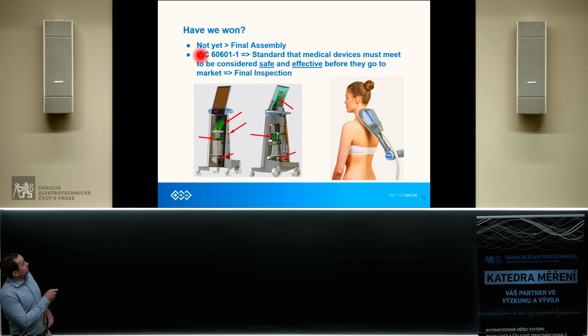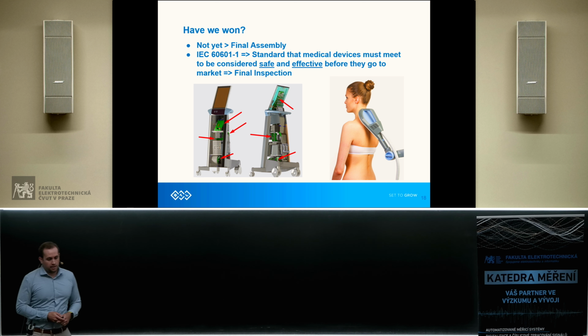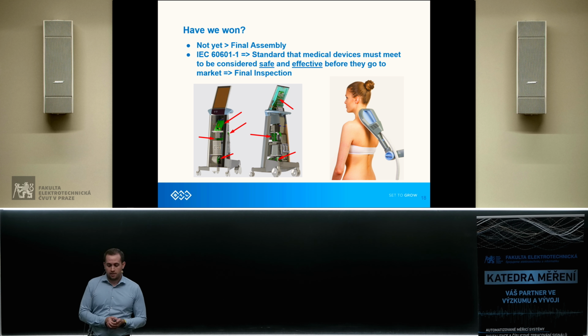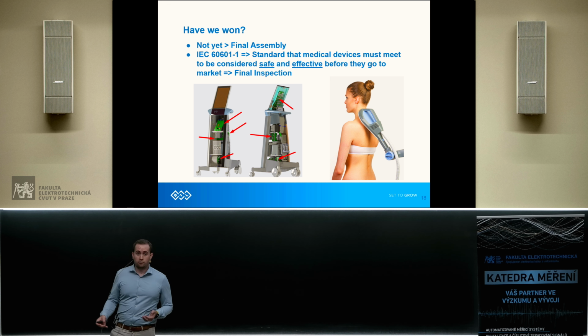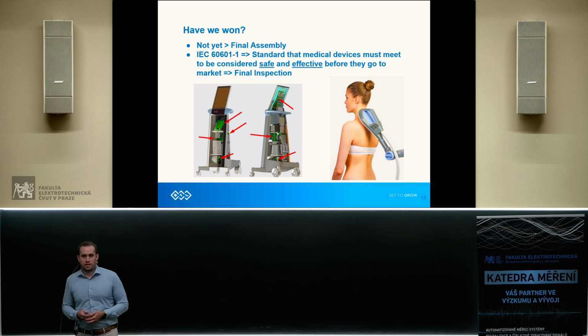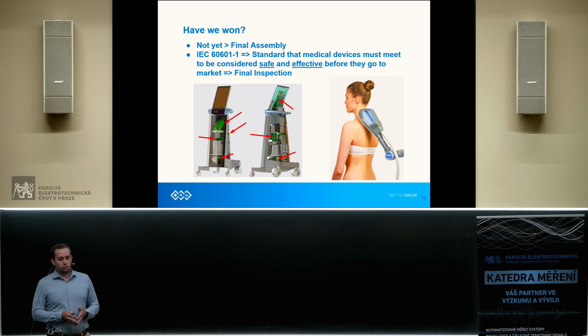And we have some medical standard, IEC 60601-1. It says that all medical devices must meet this standard, and all devices have to be safe and effective. Basically, it means that if you have a microwave device which does RF, and it should do 300 watts in the manual, you should be sure that it does 300 watts. If you have a magnet or that SIS system with a magnetic field, 2 Teslas, you need to prove that each particular machine does 2 Teslas.